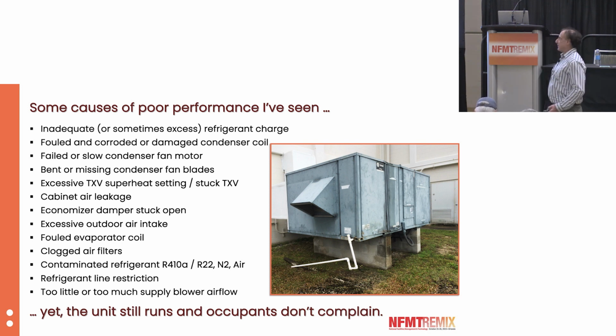Maybe a blade missing off the fan. The TXV superheat setting is way too high. Cabinets get rusty, air leakage. The outdoor air damper could be stuck open, clogged filters, contaminated refrigerant. But even with this kind of stuff, again, if you have an oversized unit, it could still provide adequate cooling. Maybe the humidity levels will be a little high. Maybe it'll be in the upper 70s and people won't be super happy, but it isn't going to be an emergency and it might not get attention.